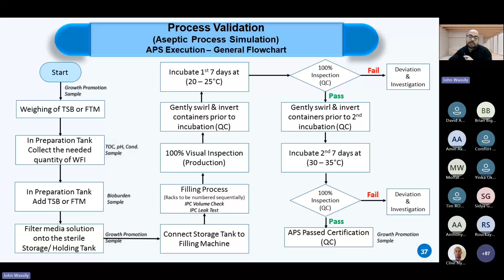After this, 100% inspection of all the filled units after the 14 days incubation shall take place in the QC lab, and be sure that no single unit is turbid, because the turbidity of any single unit will mean that a microbial growth or a fungal growth took place. And if any turbidity or microbial or fungal growth took place, this means a failure. And in case of failure, this will mean that the process is not valid for use for the routine production of vaccines.